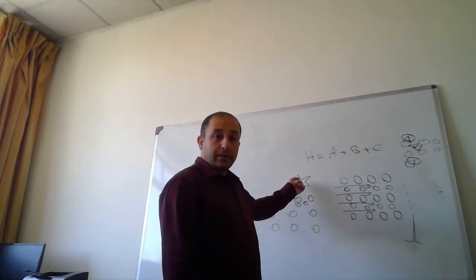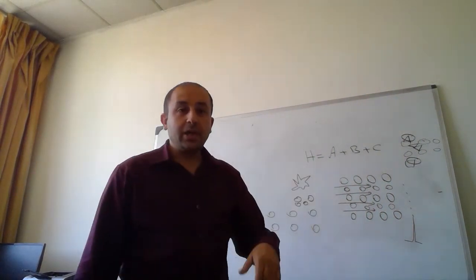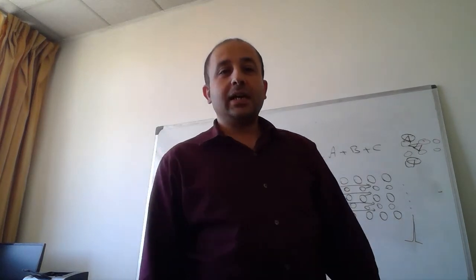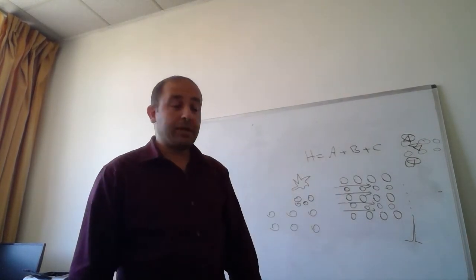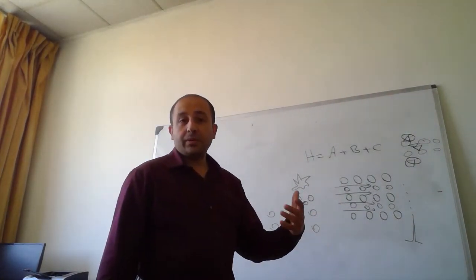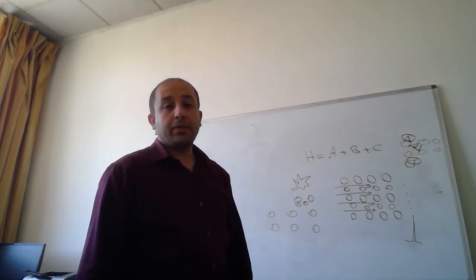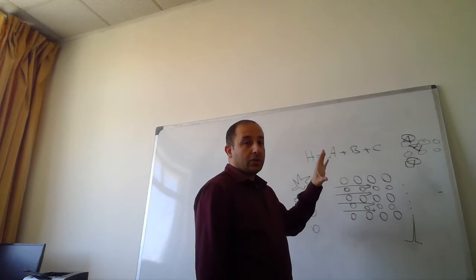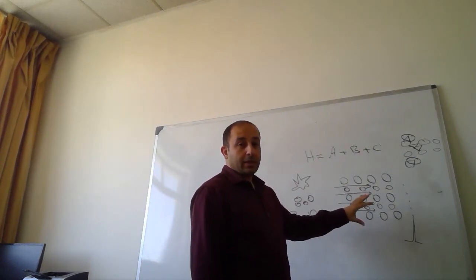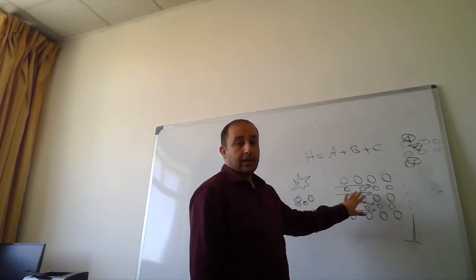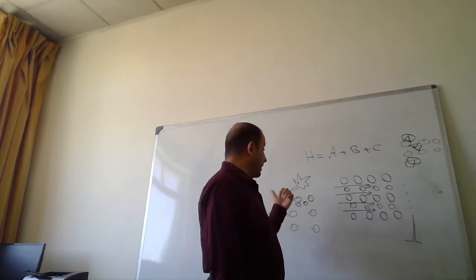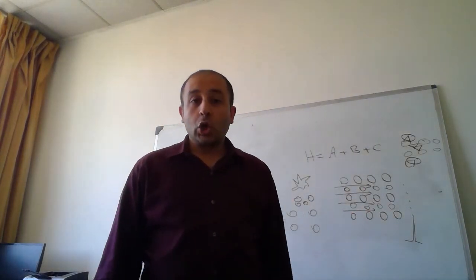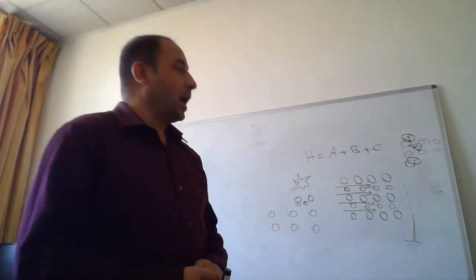If you have irregular particles with high pressure, you might have some degradation of these particles, and you will end up with bad performance of the column. So try to have them spherical, identical in size, and compressed and filled under high pressure by the manufacturer.